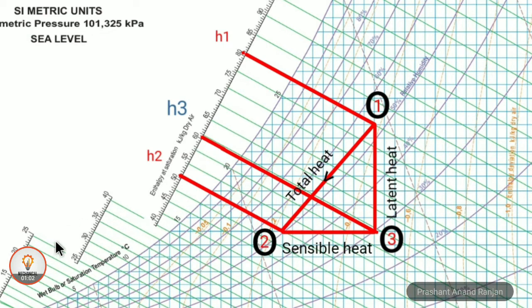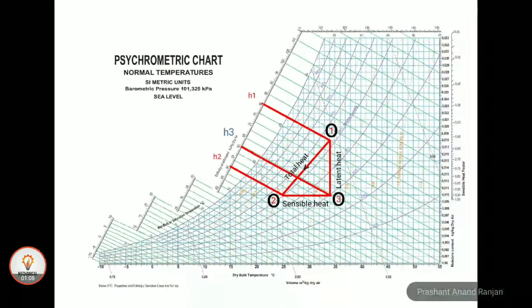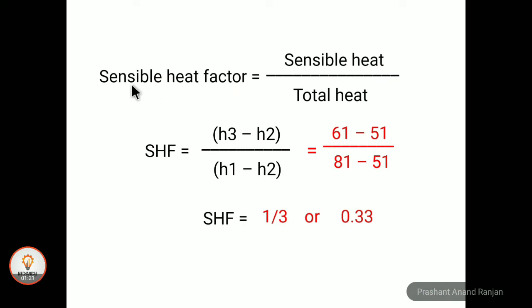Now by going by the definition of sensible heat factor, we can easily calculate the sensible heat factor value, which is sensible heat upon total heat. Sensible heat is equal to H3 minus H2, which is enthalpy at point 3 minus enthalpy at point 2, divided by H1 minus H2, which is enthalpy at point 1 minus enthalpy at point 2, which comes out to be 1 by 3 or 0.33.